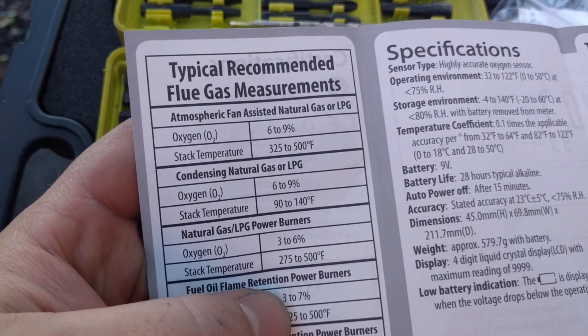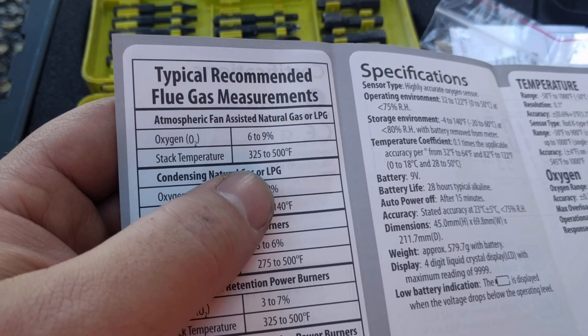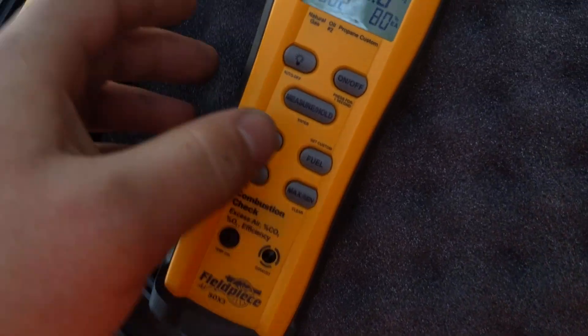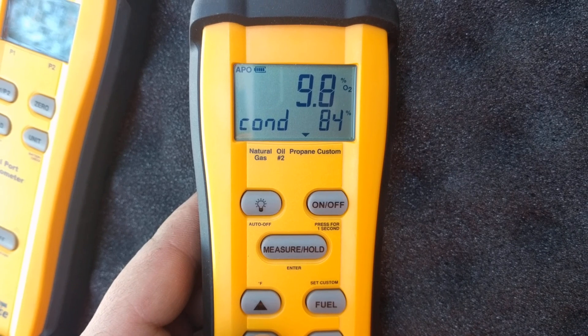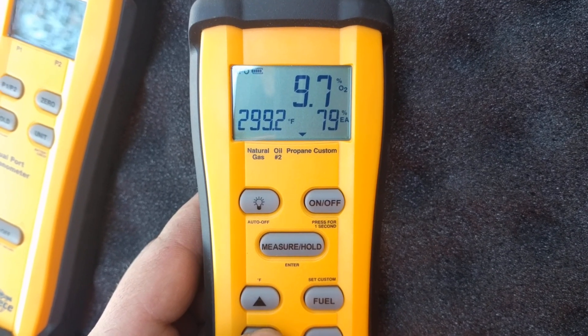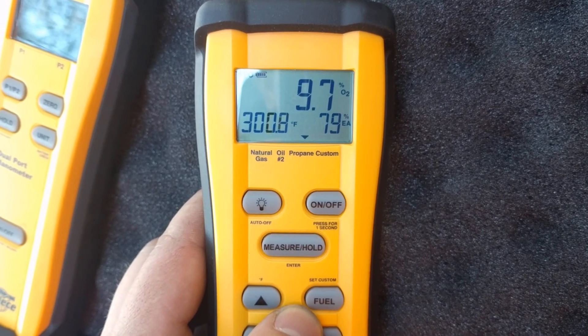Let's make sure our probe is adequately placed here — mid-stream, pretty decent. Typical recommended flue gas measurements: we want 6 to 9% oxygen, stack temp between 325 and 500°F for fan-assisted LPG. We're running at 82% efficiency. Our O2 is a little higher, which means we're not getting our full fuel going through the burners. Stack temp is up but still a little low, still climbing.